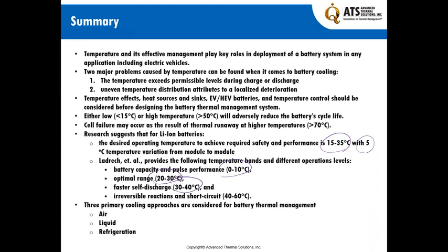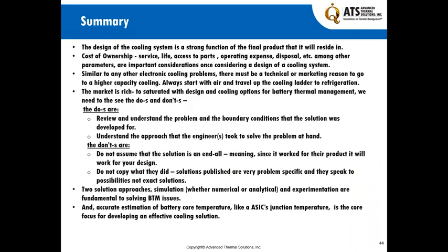There are three primary cooling approaches considered for battery thermal management at this junction: air, liquid, and refrigeration. Every one of them has branches associated with it. Air cooling could have a PCM, heat pipe. Liquid cooling could have a PCM and some sort of system-level cooling, refrigeration, etc. So design of the cooling system is a strong function of the final product it will reside in.